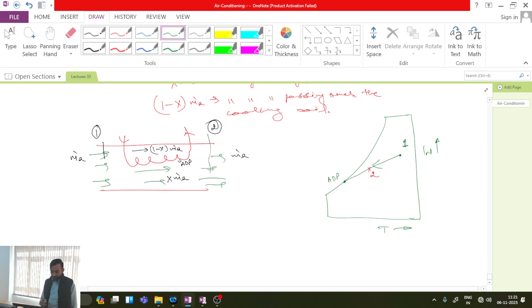Now if you assume that the state here was 1, the cooling coil temperature is ADP and the state at the exit is 2, then the air which comes in direct contact with the cooling coil will obviously have a temperature equal to that of the cooling coil. So 1 minus x into m dot A amount of air, multiplied by Cp of moist air, will have energy content equal to that at TADP, because it comes in perfect contact with the cooling coil, so it must reach the temperature of the cooling coil, plus x amount of m dot A air has not participated in the cooling process because it has not come in contact with the cooling coil. So if it entered with enthalpy 1, it will also leave with enthalpy 1.